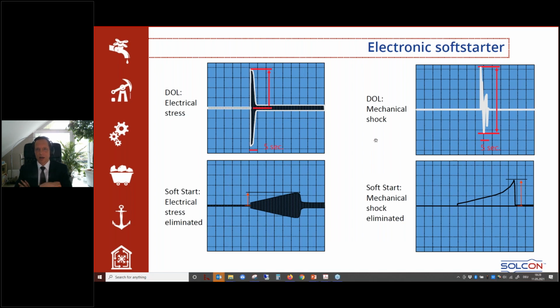Some effects on the electronic soft starting. You see here on the left-hand side the electrical stress, especially on the winding you are switching on. And the winding is seeing a certain electrical and mechanical stress, and also other mechanical equipment. You have quite a mechanical shock. You have a torque which is higher than nominal torque, and it takes some time till the mechanical equipment is back to normal. With soft starting, you are avoiding both stress on the winding and stress on the mechanical equipment.